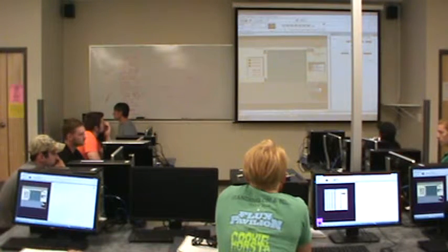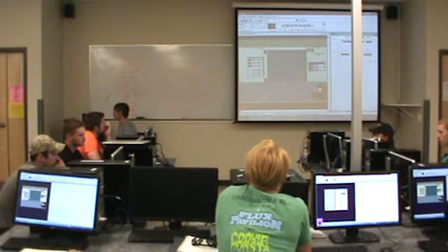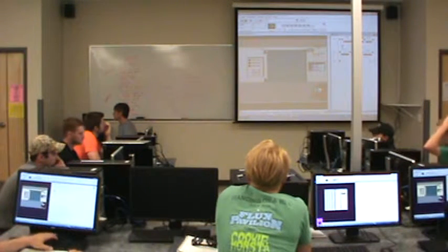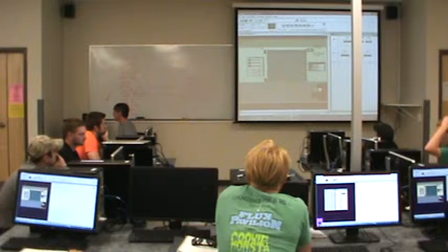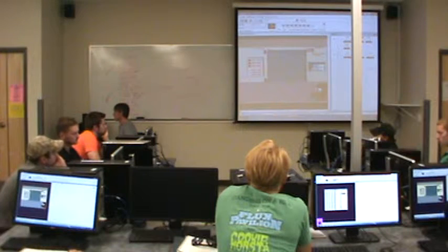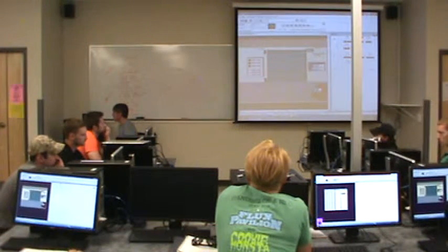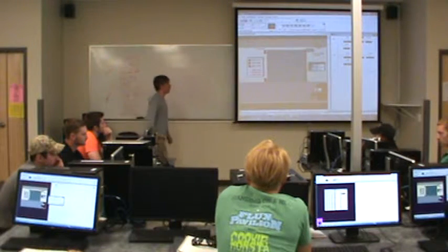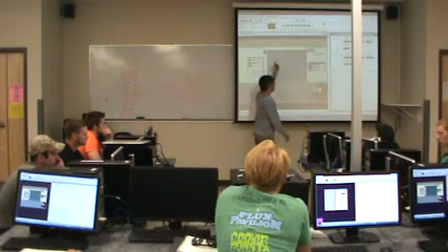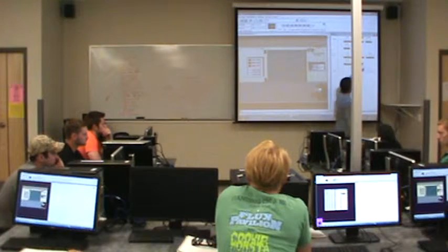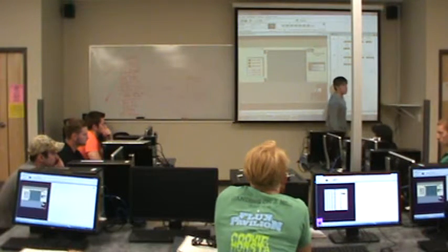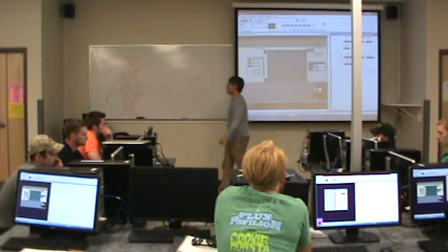Let's see, we'll put a branch around the open button so I don't have to hold it down. Put another set of contacts down here and reference the motor up. Since I don't want to hold the close button either, I'll do the same thing. All I'm doing is branching around the button itself and referencing the output address in order to create a latch. This latch will be nicely broken as soon as the door reaches the top limit switch. I left it outside of the door, so it's going to break the latch for me. Okay? So watch and see what happens.